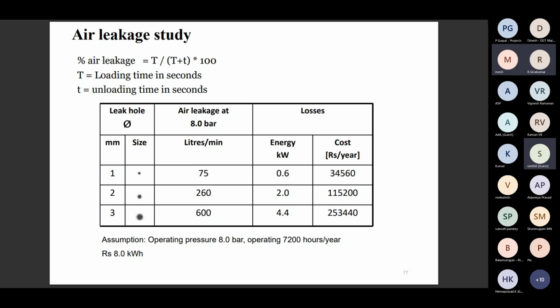This should be done only during the plant idle condition. That is the only time we are able to say. Normally maintenance people conduct this air leakage study during shutdown time or on Sundays. They take the loading and unloading time with a watch timer, to see how much loading and unloading takes place in 1 hour.